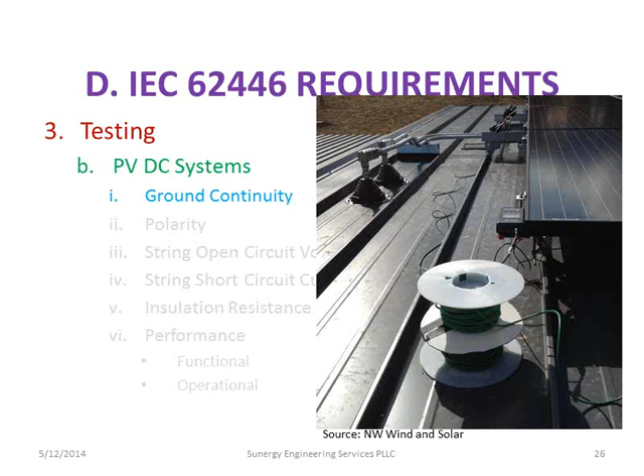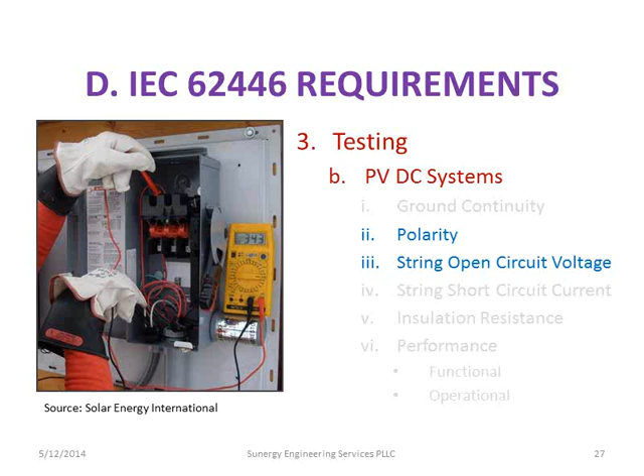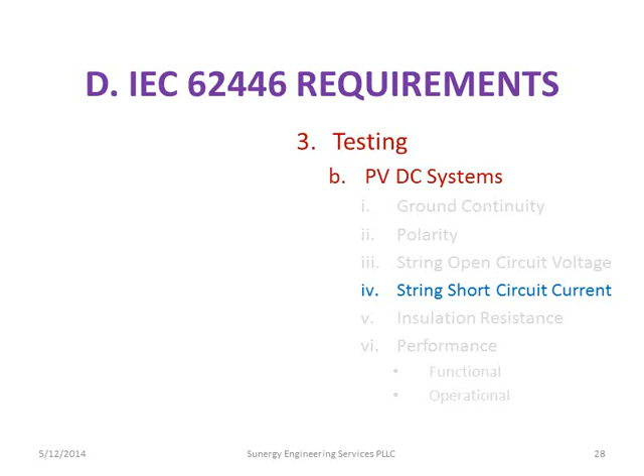And then, of course, we have to check our polarity and string open circuit voltage, which is easy to do with a normal voltmeter, not a problem at all. Some of the tools that I have up here do that automatically for you, which is really nice too. And this is the tough one. This is the one that's required by IEC. They want you to do the string, whatever the string length is, they want you to do a short circuit current.